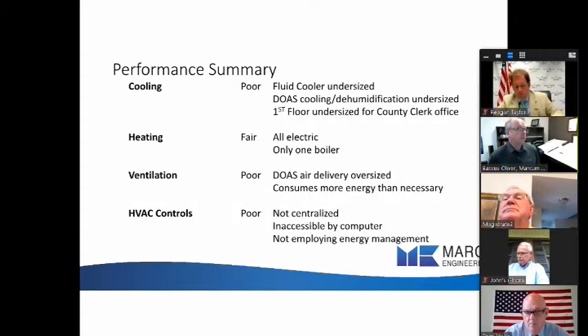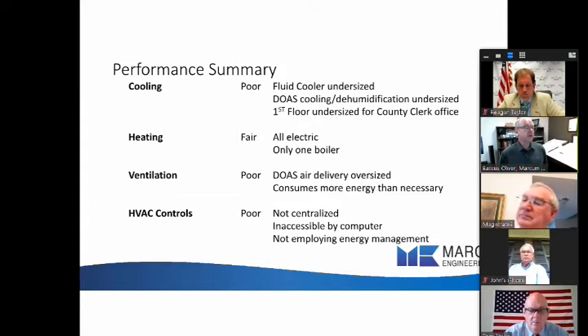So I'm going to summarize the performance. Our cooling system is poor. The fluid cooler is undersized. The DOAS system is undersized. It's also oversized on air, but it's undersized on being able to cool and dehumidify, and that's allowing humidity into the building. And then we have a first floor where the county clerk may move in later, and that area is undersized to support the county clerk office.